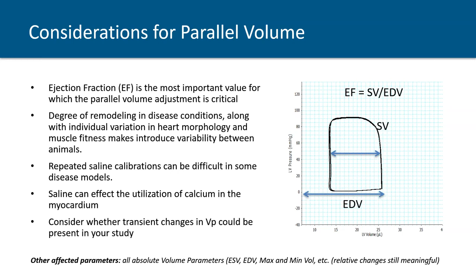So as we're close to wrapping up, just a couple of quick points. People spend an enormous amount of time, and these calibration techniques are obviously quite challenging to do for each animal, but equally as important, once you have a fully calibrated pressure volume loop, when it comes time to doing your analysis, it's equally as important to understand some of the techniques that are applied to this analysis, because that could introduce even more variability than perhaps not calibrating your system to begin with. Or if you've gone through the trouble of calibrating your system, you've now introduced so much variability by some of the analysis techniques that you've essentially nullified your calibrations.